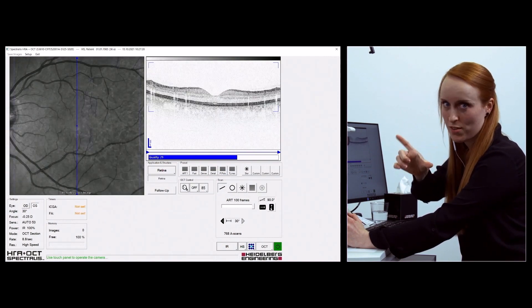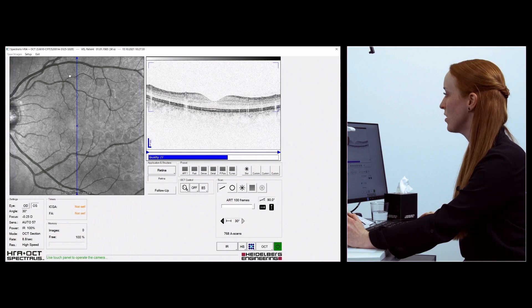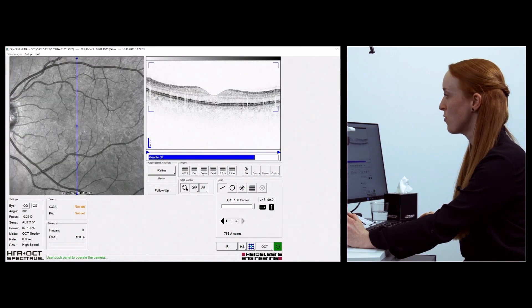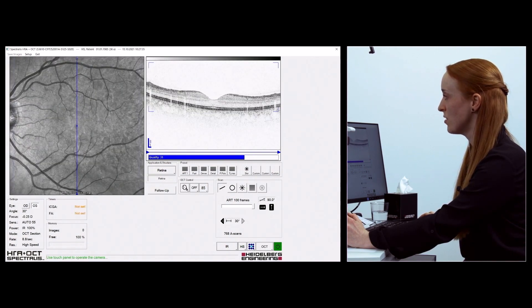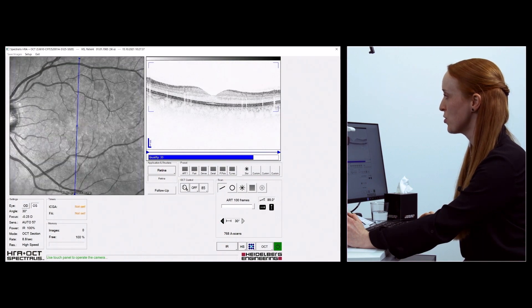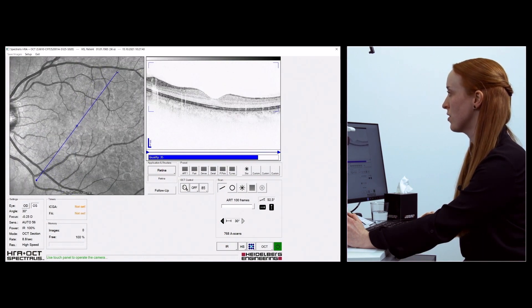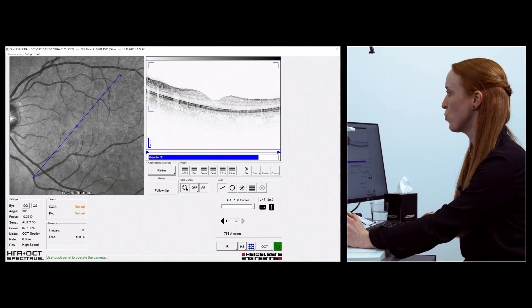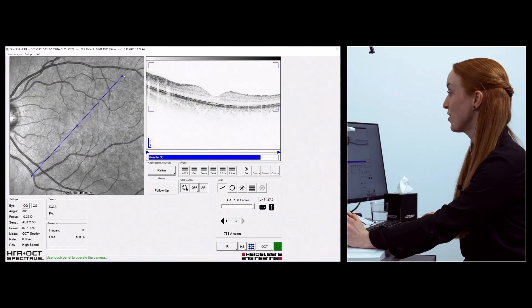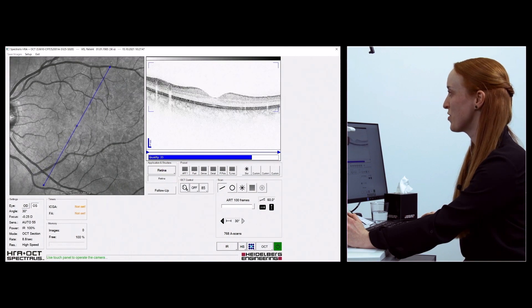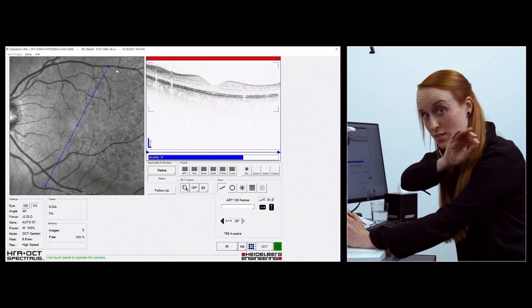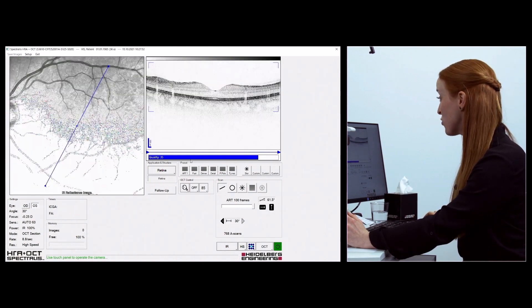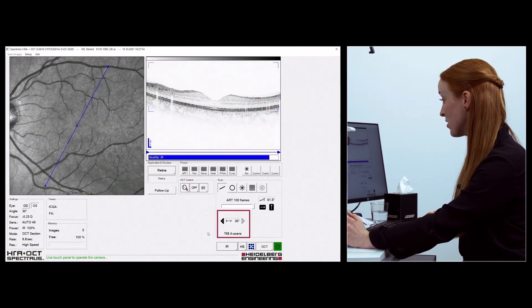But what you can do then is grab the arrow of your scan in your infrared reference image and just turn this scan to the direction while watching your OCT image, and hopefully it reaches one direction where it's really settled evenly.